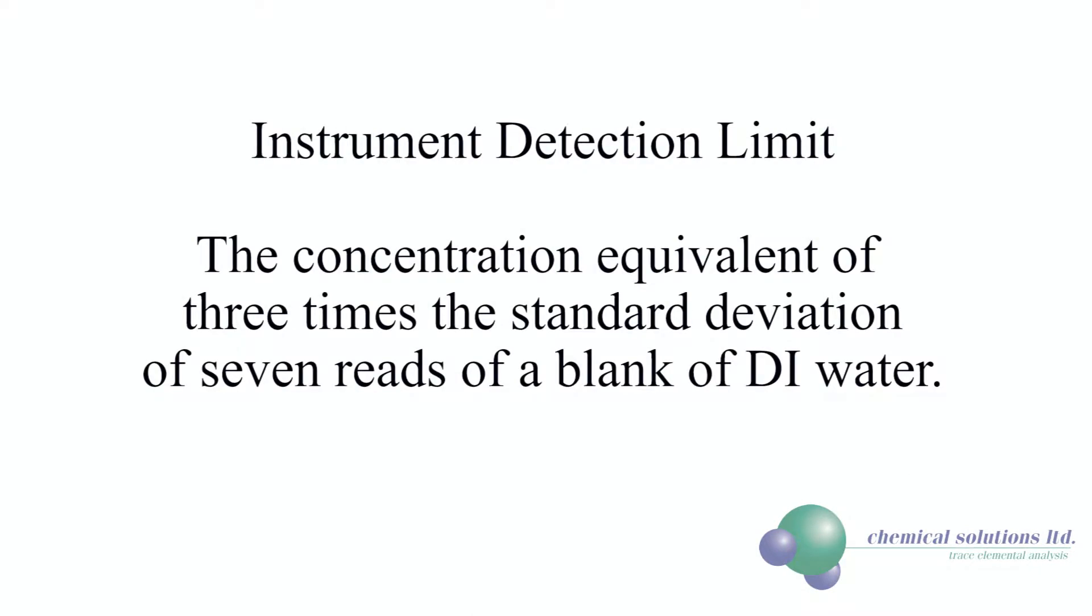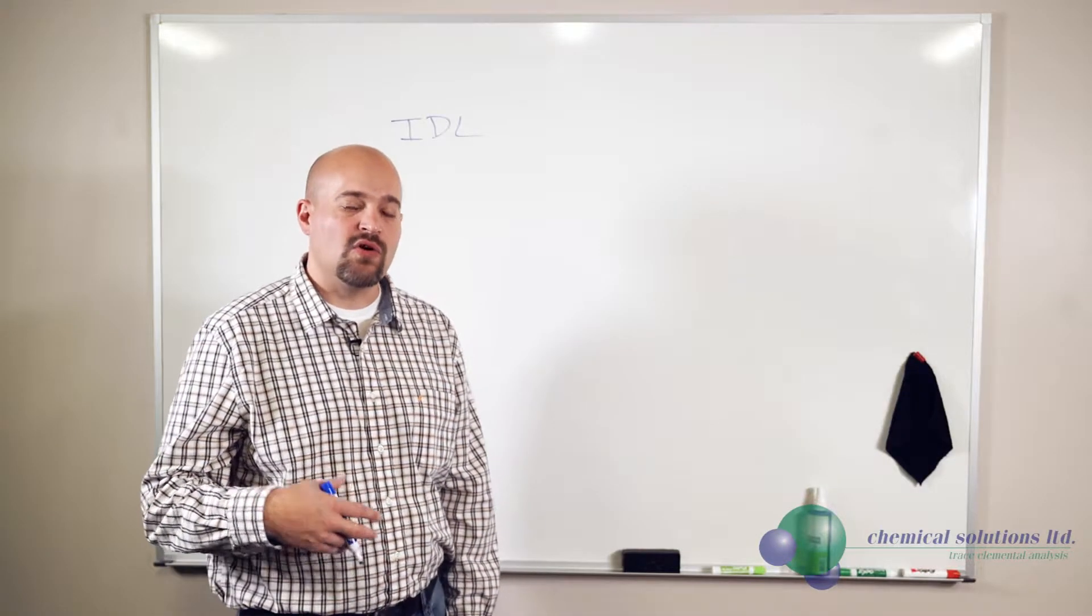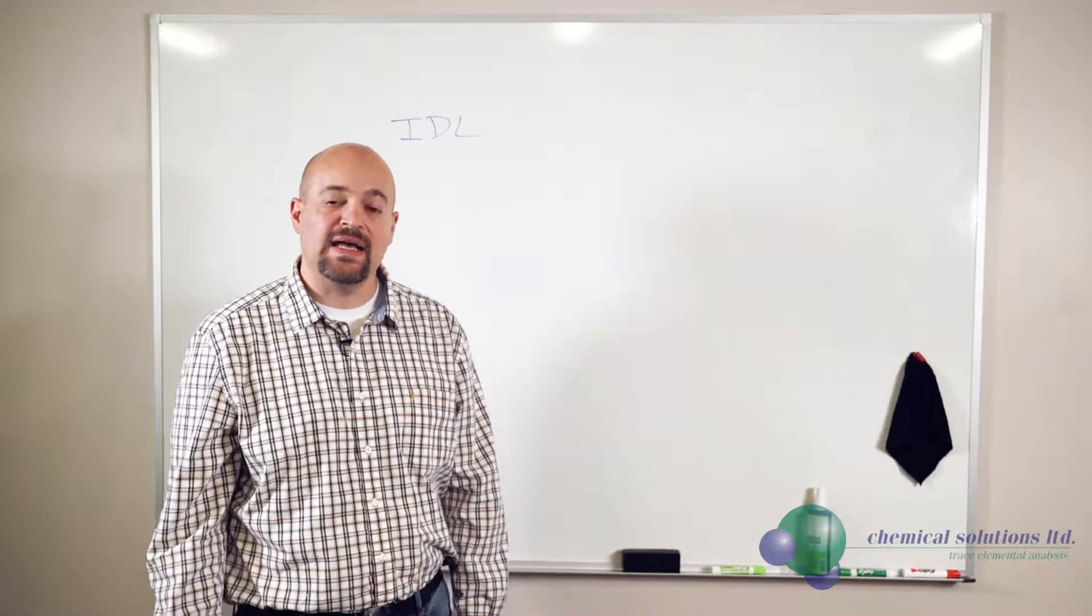An IDL is defined at Chemical Solutions as the concentration equivalent of three times the standard deviation of seven reads of a blank of DI water. So that's how we're going to calculate or one way we're going to calculate an IDL.